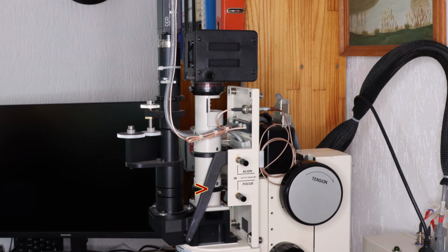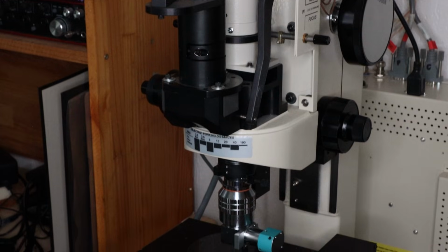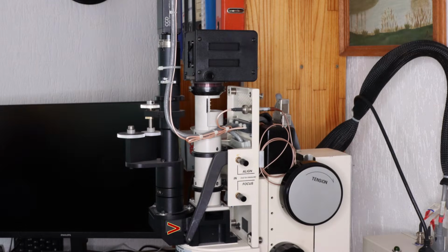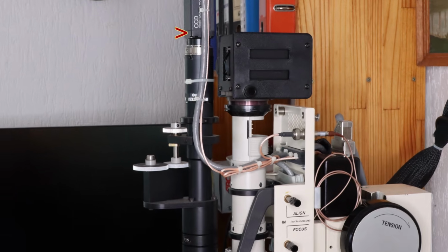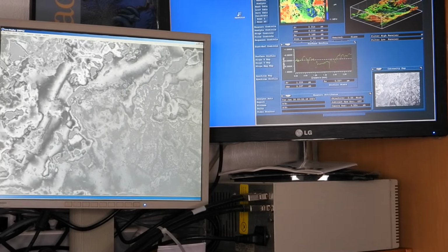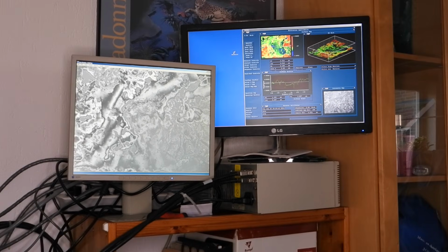The spatially coherent light then goes straight through a beam splitter and then into the microscope objective where the interference is generated. It then returns to the beam splitter and is reflected to a camera. And the camera has a zoom lens that allows for setting an additional image magnification.